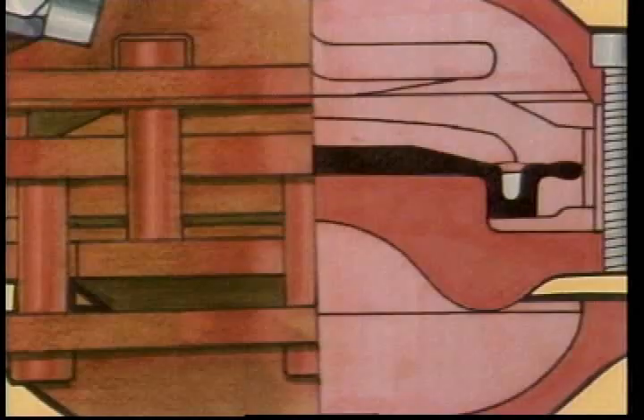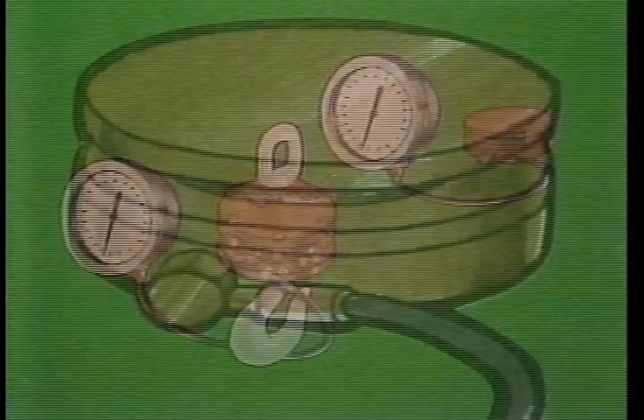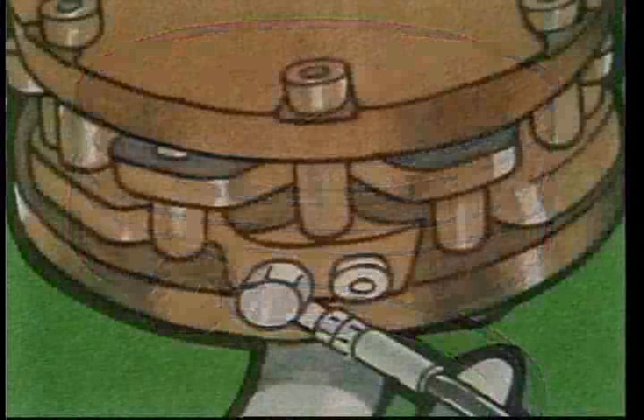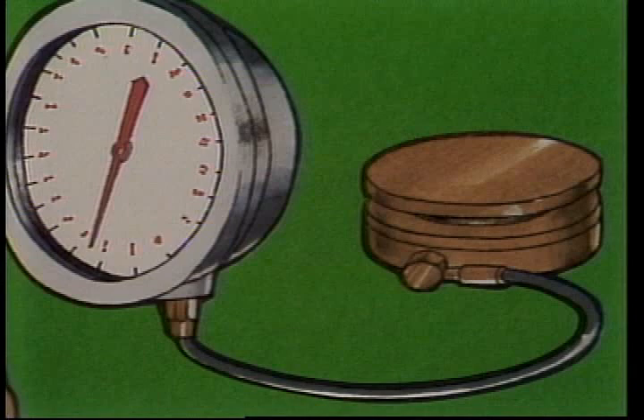A load cell, as important as it is, really isn't that complex in design. It's a simple hydraulic device with only one moving part — a diaphragm. This diaphragm can transmit a tension or compression load in pounds to a local or remote pressure gauge. Because its accuracy and sensitivity are superior to other types of load indicators, load cells are a must in our business. There are two types: the compression system and the tension system. All load cells are compression measurement devices, but with auxiliary hardware they can also measure tension loads with extreme accuracy.